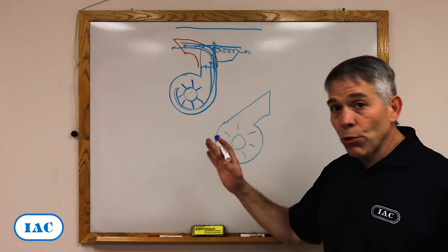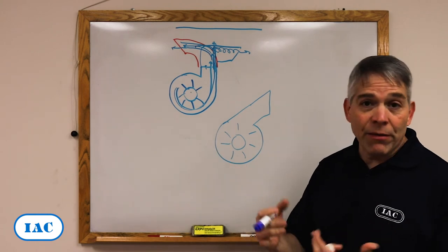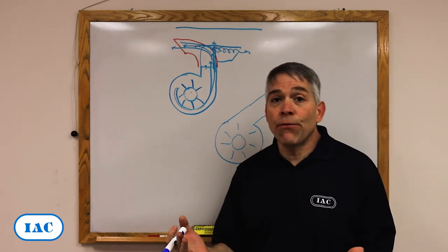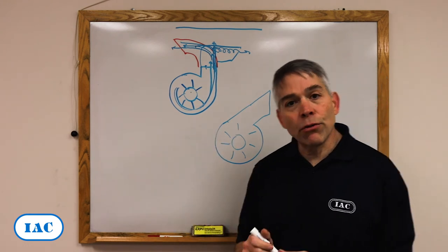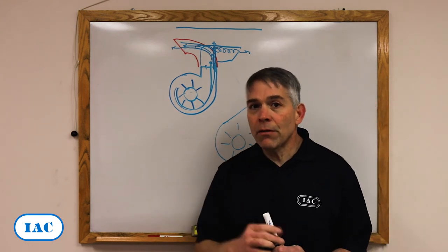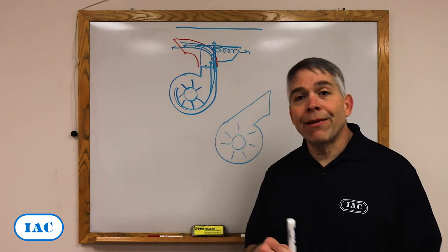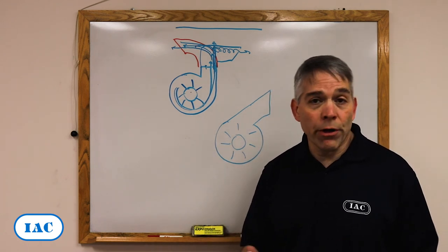I have seen fans that lose a lot of efficiency. Basically, if it's designed for 10,000 CFM, you will get 6,000 because the outlet is not positioned properly. So think about these things, and I'm sure it will help you get the most out of your equipment, which you already paid for.